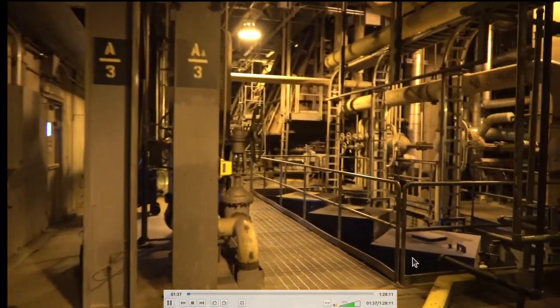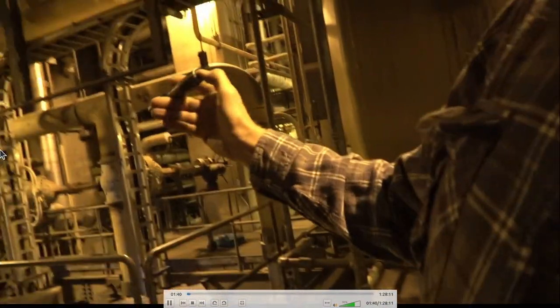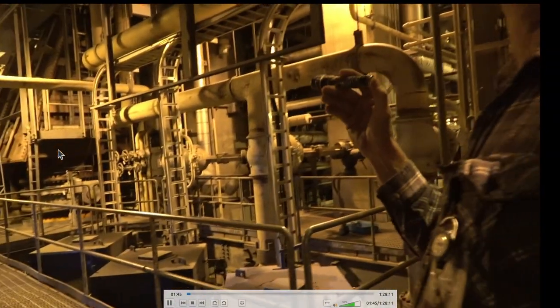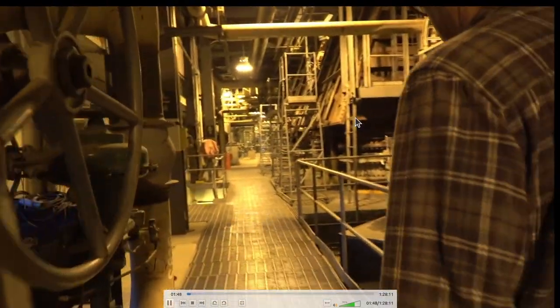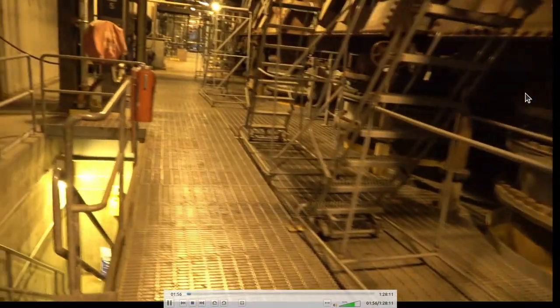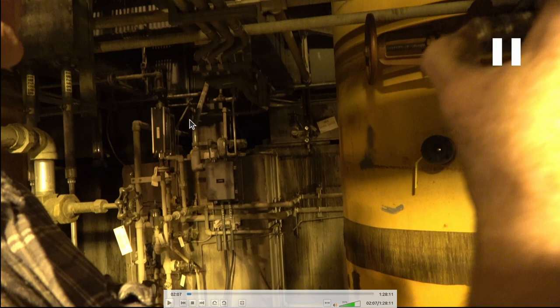Here are the condensate pumps and condensate discharge valves. The condensate heater runs about 330 pounds. This is the surface condenser — these are the water boxes on the two surface condensers. It takes about 180,000 gallons of water a minute for cooling. This is the condensate pit underneath. You've got water going in with two inlet lines and two outlet lines. Back here is where you check for leaks — you can sample underneath the rows of tubes to see where a potential leak is.